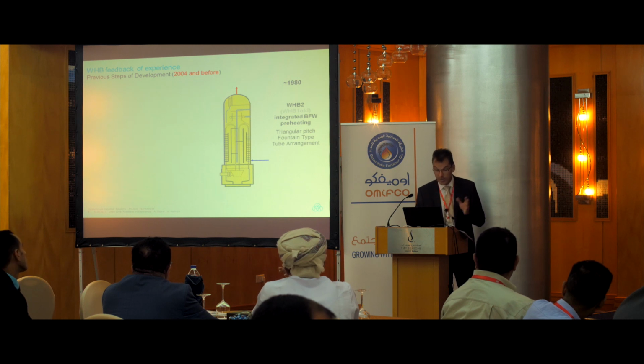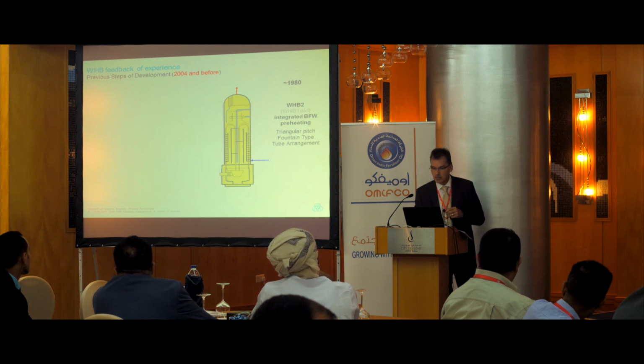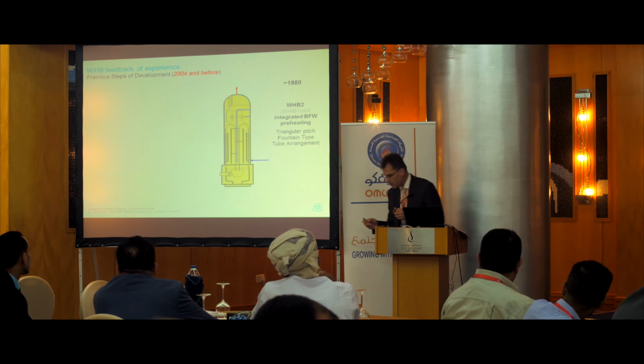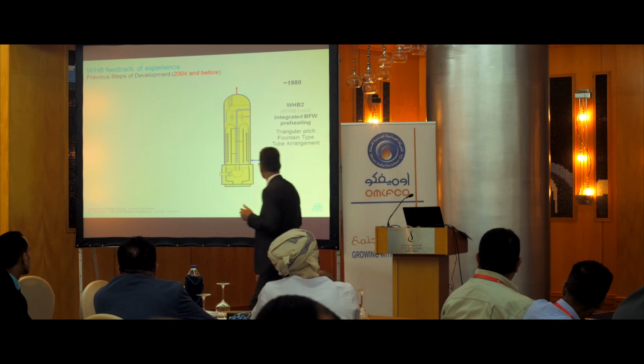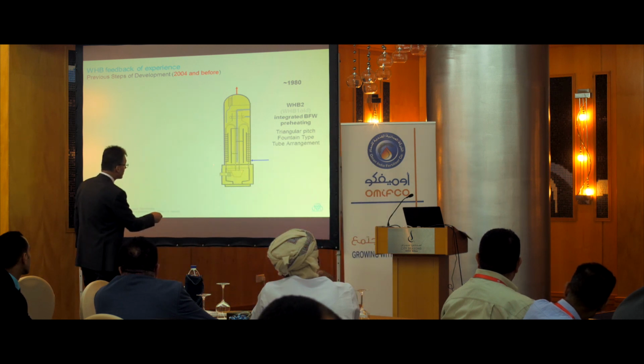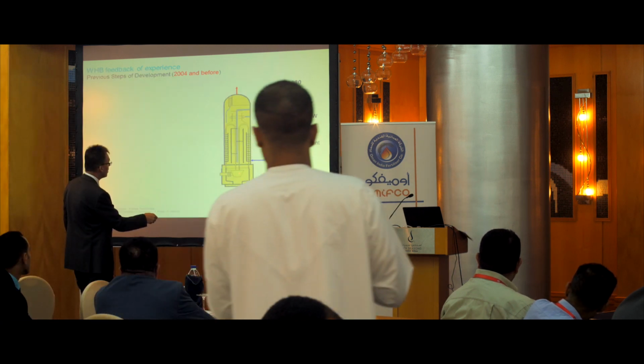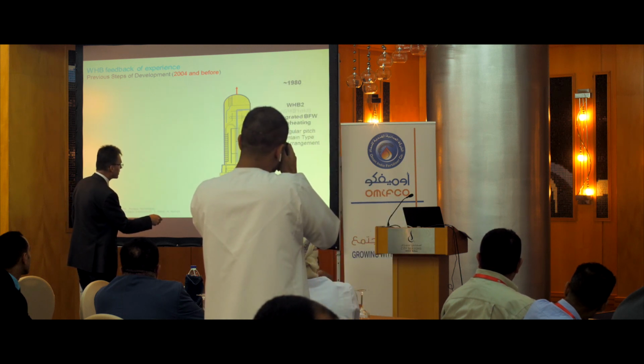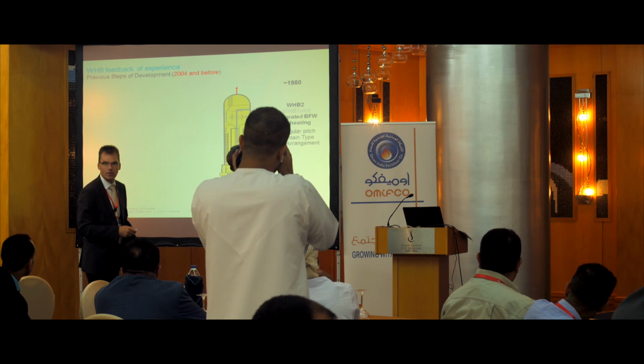It was developed already in the mid-80s, not only by Uhde, also by others, with its typical fountain-type U-tube bundle, which has kept almost unchanged since then. A fountain-type U-bundle, just why is this name so funny? It's like a water fountain. Hot gas comes in, goes up to the heat exchanger tube, comes down like water as cold gas. So this is like a fountain, therefore this name water fountain type.